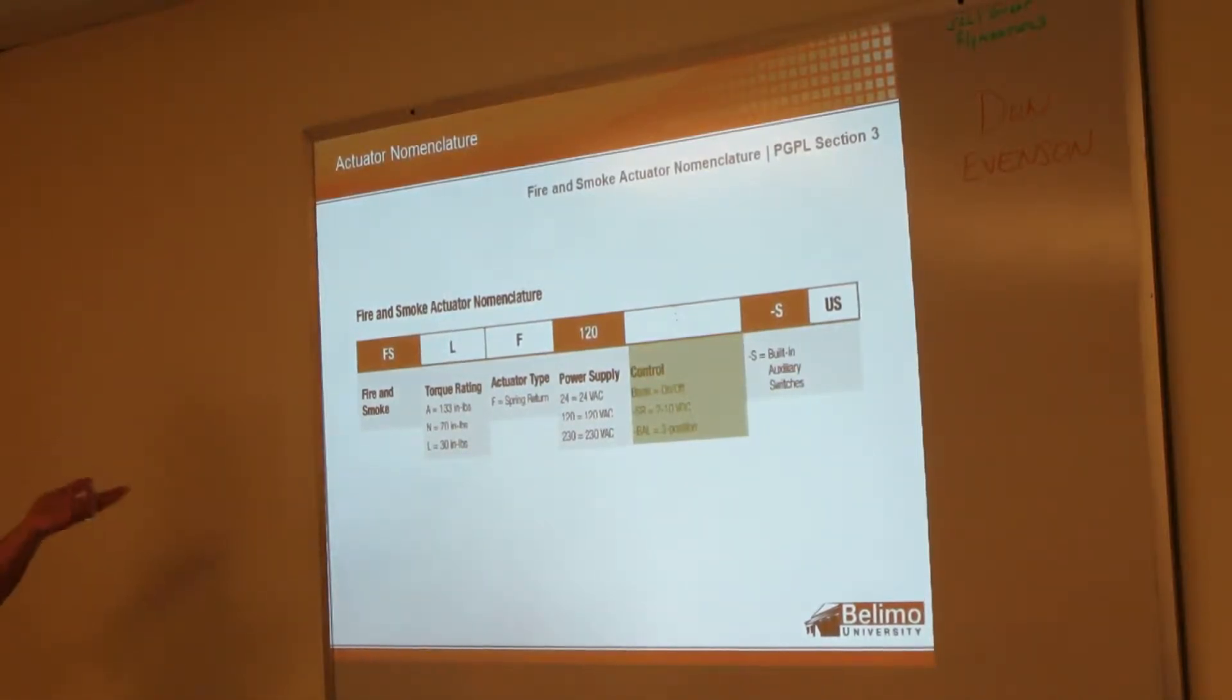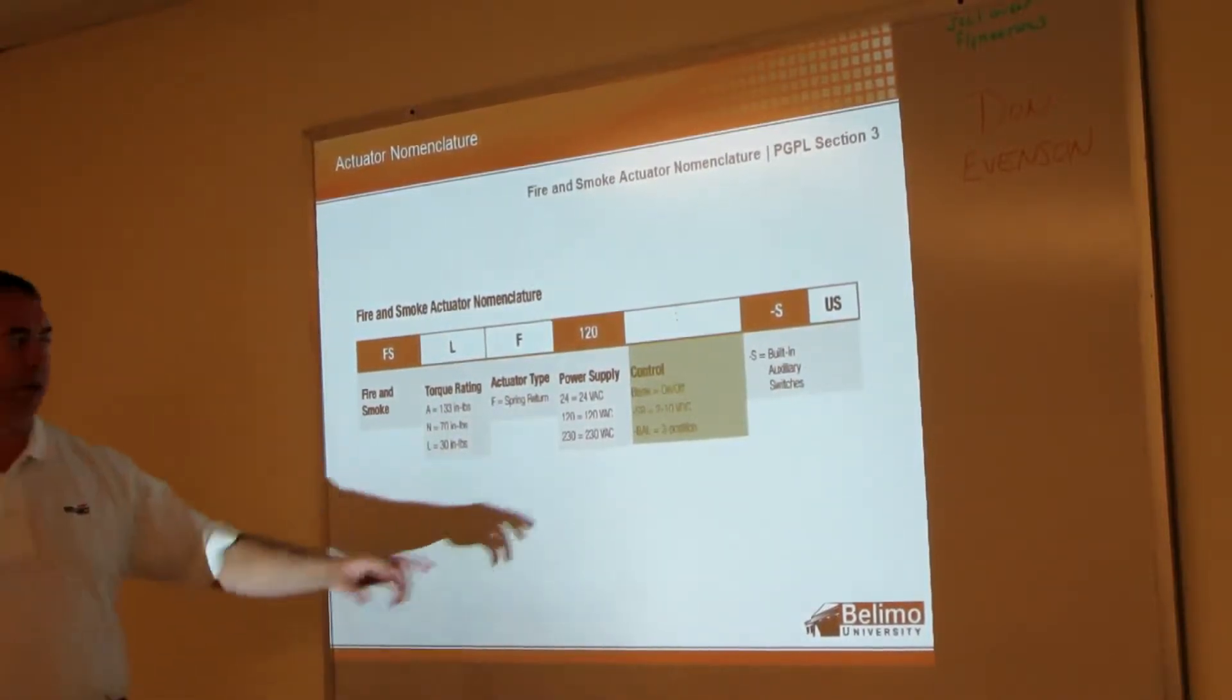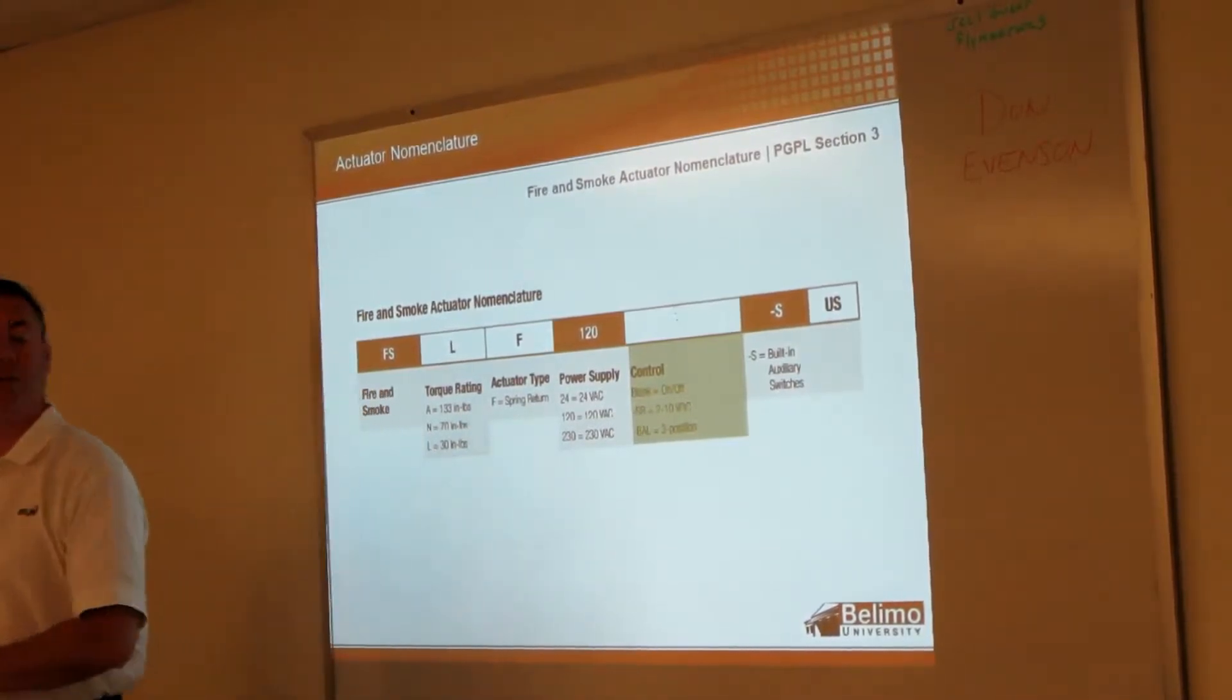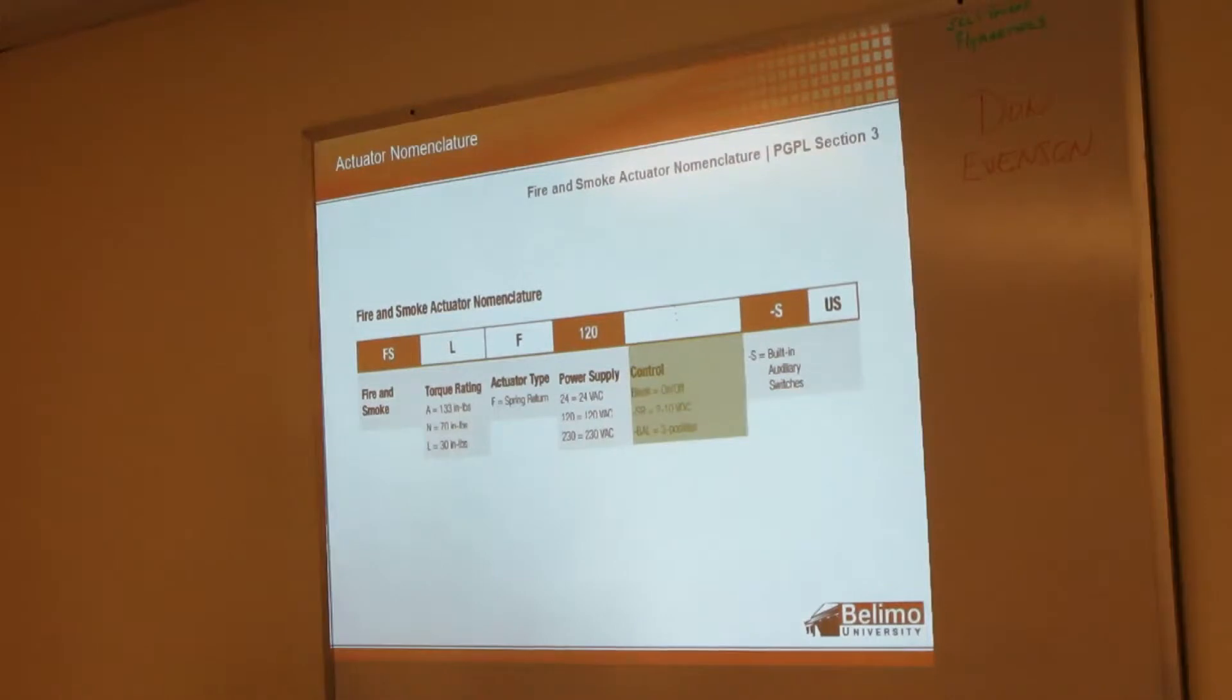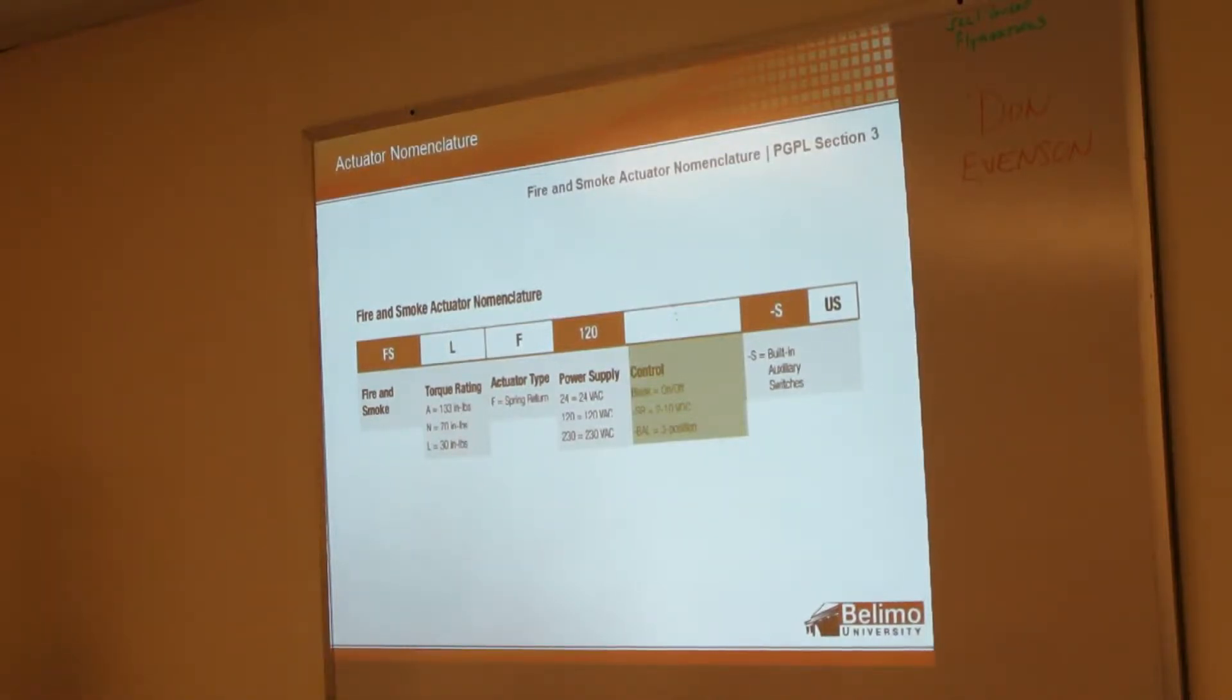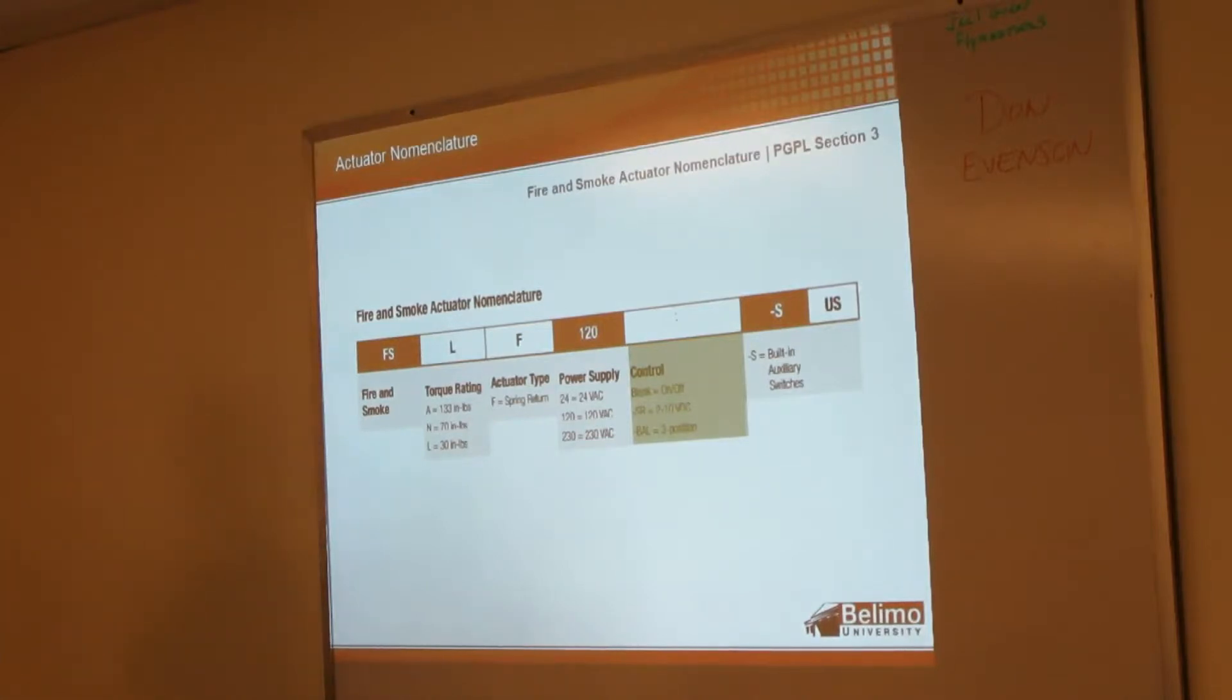On the other hand, we have a couple unique fire smoke actuators. We have a dash SR - that's our two to ten volt - and we also have a three position actuator which can be used for balancing. The two to ten volt can be used if you use a fire smoke damper as a control damper as well by using that dash SR, and then the three position dash BAL can be used as a balancing damper as well as the fire smoke damper.